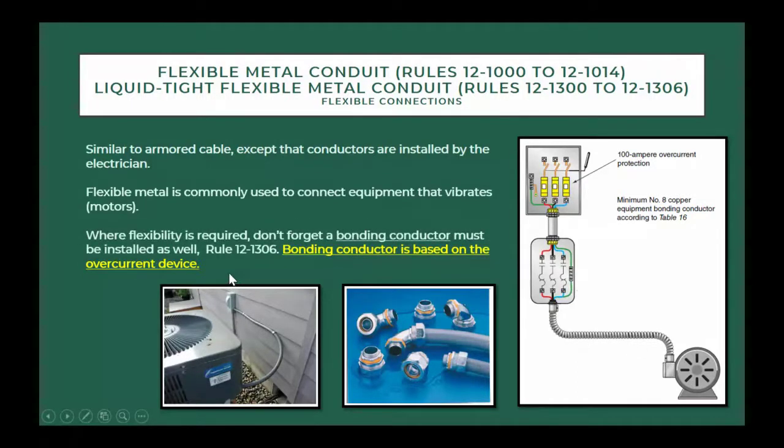So remember, one thing you got to remember is where you use this type of flexible, where the electrician's inserting the conductors, you have to provide a bonding conductor based on the overcurrent device.